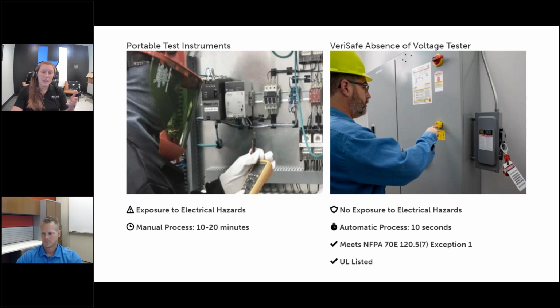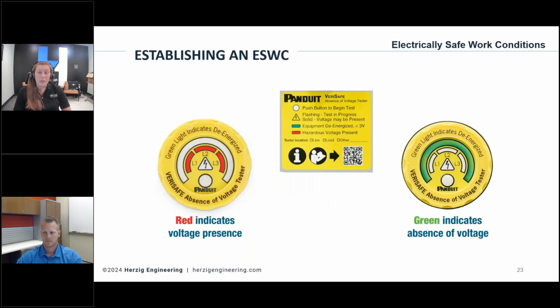I tend to bring these kinds of things up whenever I see really dangerous equipment. Like if the results of a study is over 40 cals per centimeter squared and they only have 40 cals available, I'm like, all right, next time you have a shutdown, you really should get one of these things installed. Especially after the utility, we don't have control over their protective devices, so there's not much we can do to help lower the hazard at the mains of your equipment. That's my number 1 place that I would suggest putting these kinds of things, but you can put them everywhere. Frequently accessed equipment, the more often you have to do this live, dead, live check, you push a button, it'll do it for you. We'll get into that more, but I'll let Alan explain that a lot more. He knows more about that stuff.